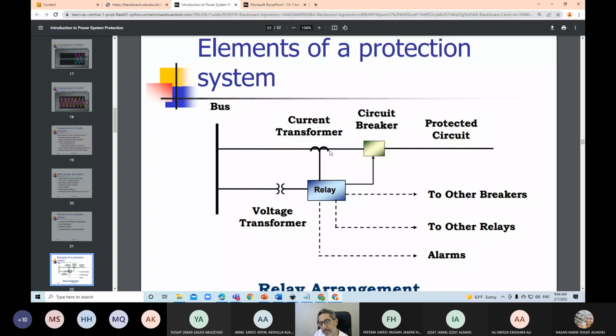And the relay here is the piece of equipment that, based on these two pieces of information, knows whether this is a normal situation or there is a fault condition. Now, if this is a fault condition, it will give a command to this circuit breaker to open the circuit. Sometimes it will also send a signal to other breakers to open if required. Sometimes it informs other relays that they should act, or that it has found a fault. Sometimes it gives an alarm.